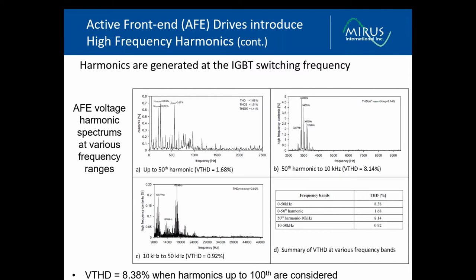And the last graph I'd like to show you is the importance of addressing the fact that active solutions such as active front-end drives or active harmonic filters do introduce harmonics at higher frequencies. So our first graph here shows us the spectrum. These are voltage measurements taken on a ship. We can see our frequency here on the x-axis going from 0 up to 2.5 kilohertz, or on a 50 hertz system, the 50th harmonic. And we can see the band here, predominantly 5th and 7th, some higher levels, but all are very, very low.